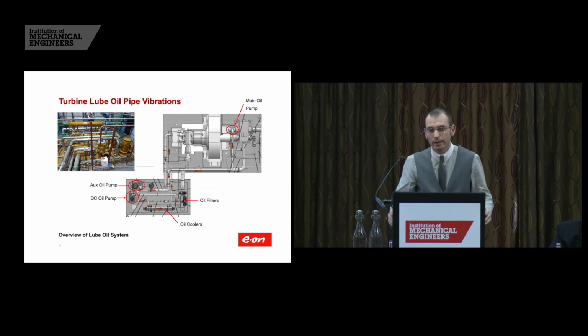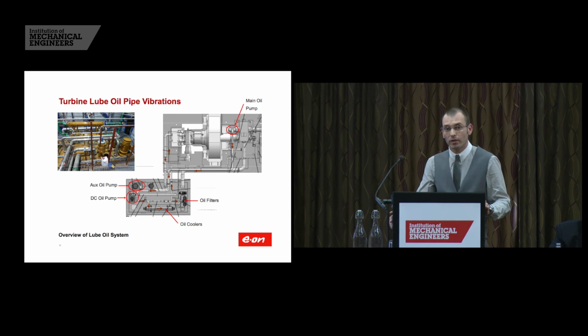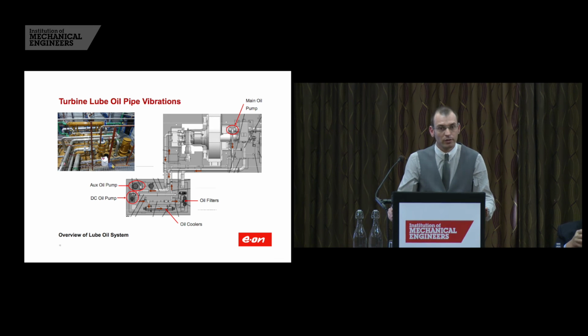However, during run-up, when both pumps are in parallel, we had severe vibrations within the lube oil system. These were visual. You could literally see them moving 10 or so mil. So the decision was made to abort the start. We sat down with the OEM and had a discussion. We ran the machine again, and the same vibration occurred. At this point, it was decided to stop and remove the main shaft-driven oil pump to investigate if there was any damage to the pump and any other aspects within the lube oil system.